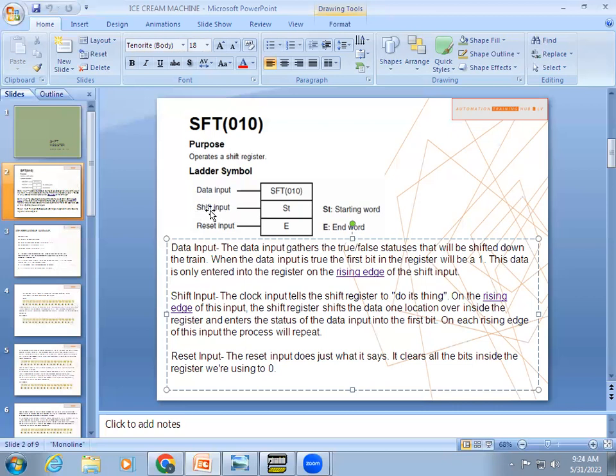Whenever the shift input gives one pulse, only then will the true or false status from the data input be accepted into the shift register. The shift input is the clock input — it tells the shift register to do its thing. If you are giving an auxiliary relay like every two seconds, one second, or half a second, it will give a pulse. Each pulse time it checks the data input status: if it is one, it will shift that status into the register; if it is zero, it will move that zero status into the register.